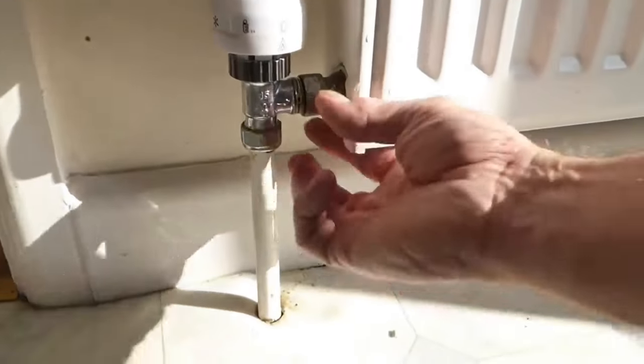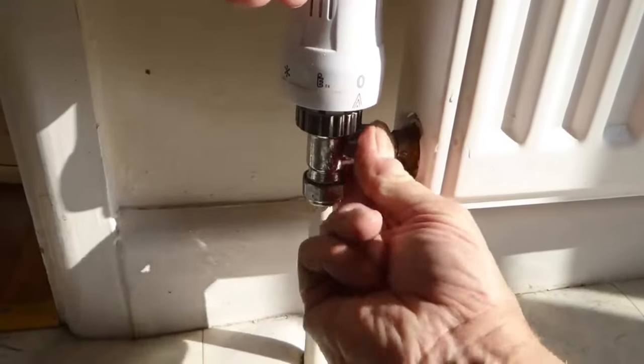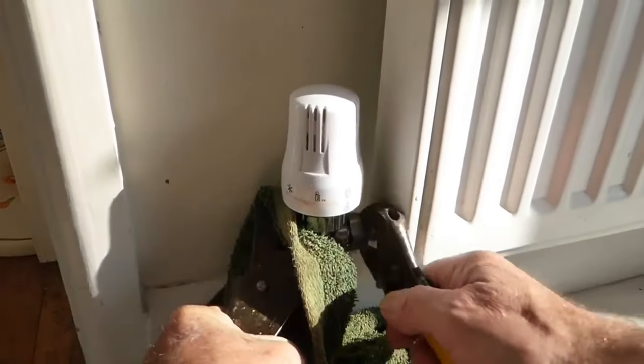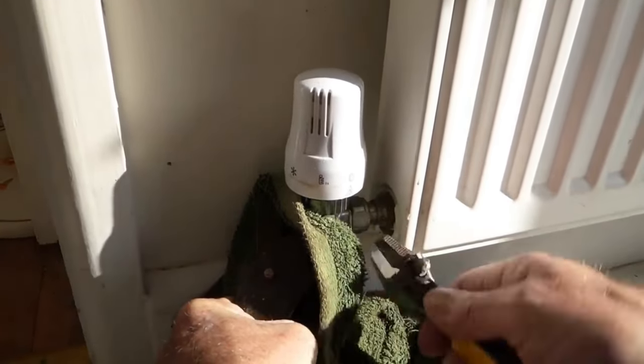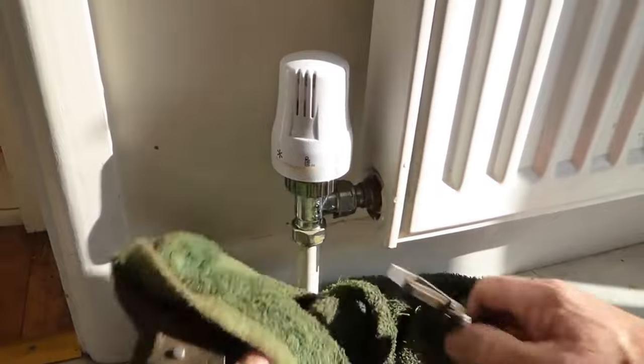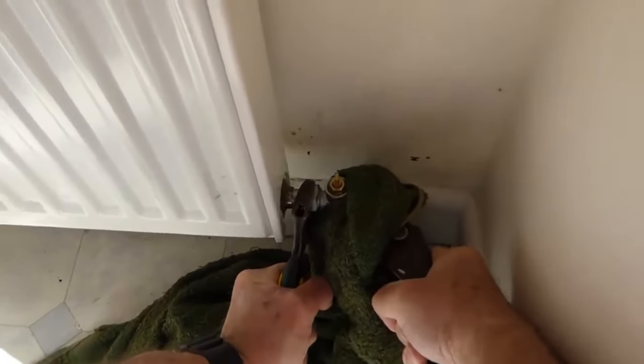Pop the pipes back in, start the union nuts by hand, then tighten them up with the spanner while holding against the valve — wrap an old towel around it to avoid scratching the chrome. Make sure both ends are started before you tighten either. For the lock shield side, turn it back the same number of turns you turned it off. Then open the bleed valve, let it bleed out, check pressure, and turn the heating back on. Hopefully it should work a dream.